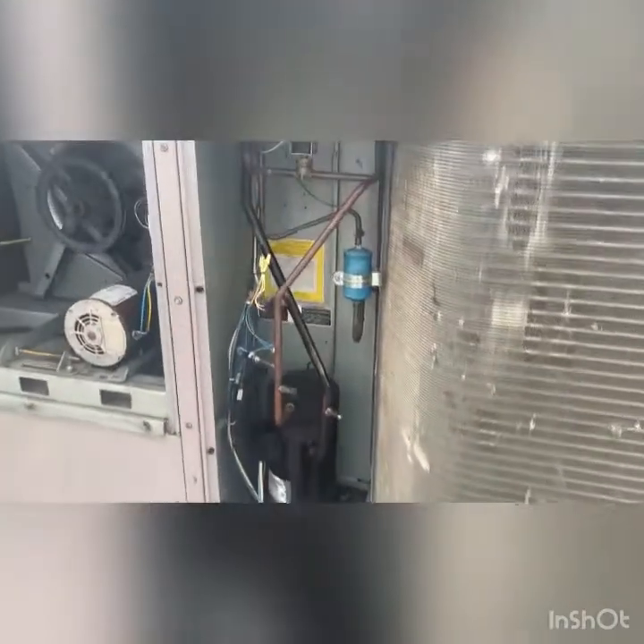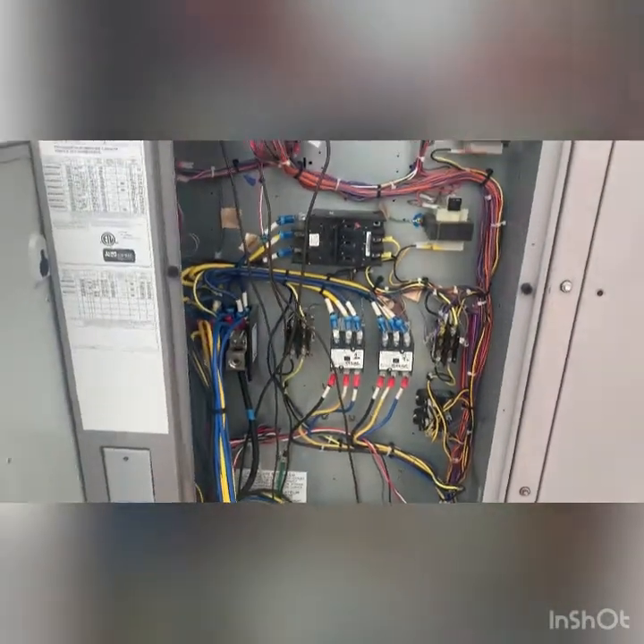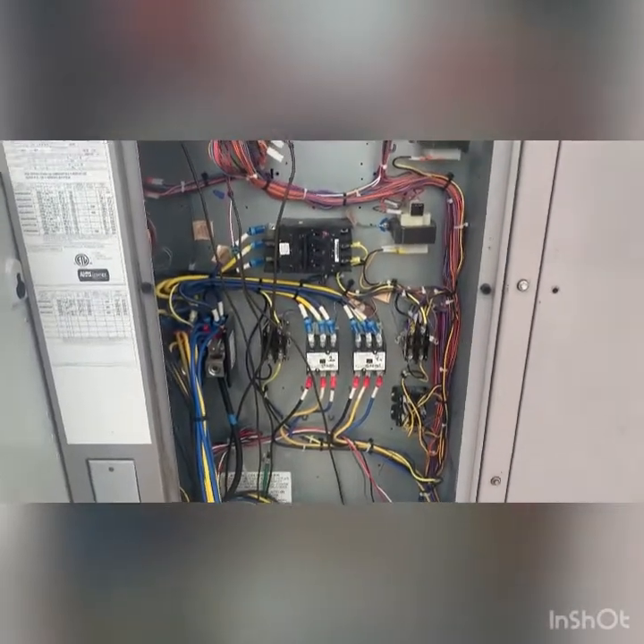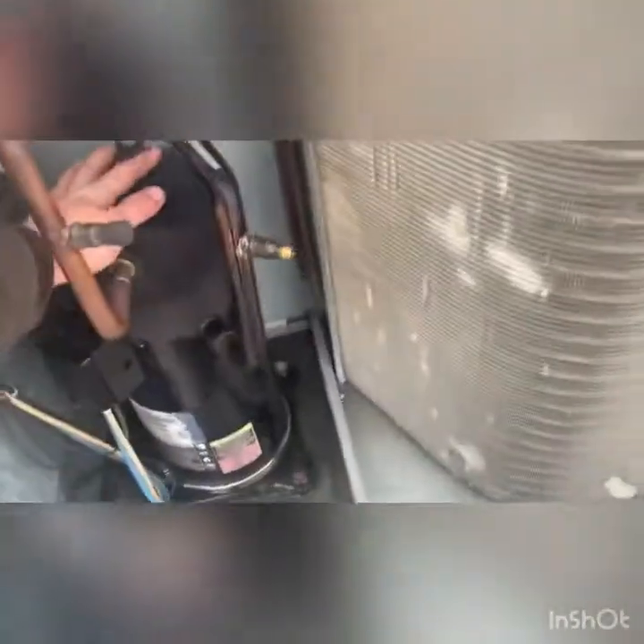The blower motor just started, it's not calling for cooling yet. We have a two-stage system — it's a stage one call and that'll pull in, you'll hear the click. The compressor will start, and the condenser fans should start. Okay, that kicked in — compressor started.